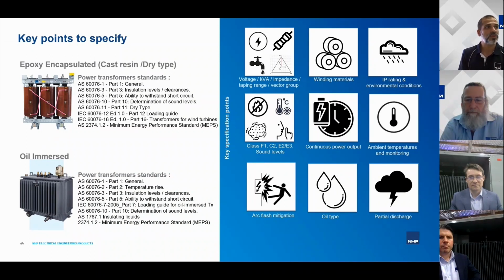But the main other parameters to look at are obviously voltage, your power ratings, your impedance, and if you have a tapping range in mind, vector grouping. Depending on where it's going and which network it's connecting to, because sometimes, depending on where you are around Australia or New Zealand, the vector grouping can be different depending on the utility it's connected to. Winding materials, that's another interesting debatable topic, and I think Sean has a good example about that, which he wanted to mention. So I'll pass you on to Sean.